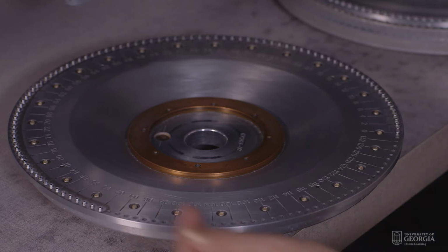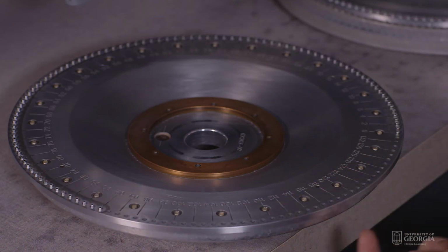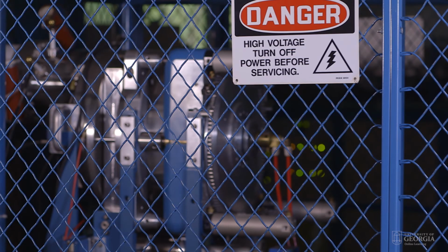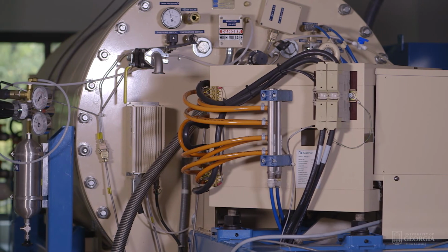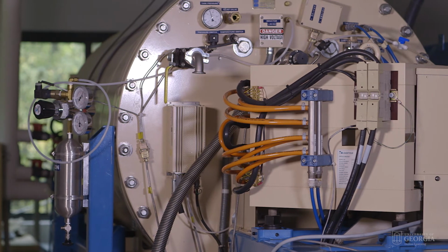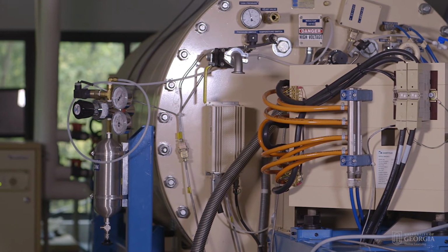We have what we call a wheel that we load onto the accelerator. A wheel holds about 133 samples of those little samples of graphite, and we load it onto the ion source, which is here on my right. We load the samples on, and one at a time, the samples are ionized. That means they're given a negative charge. And once they have a charge, we can use magnets to manipulate and move the samples through the system. So we inject this beam of negative carbon ions from the source towards an electromagnet.